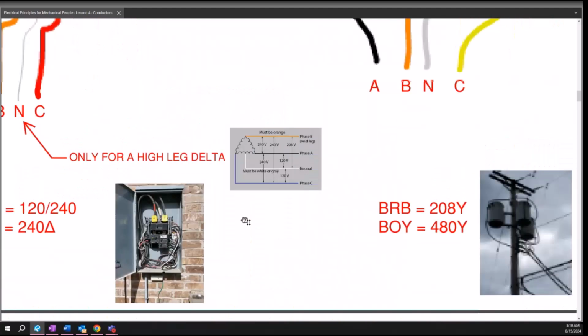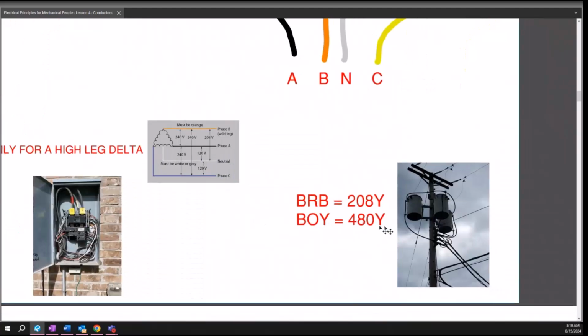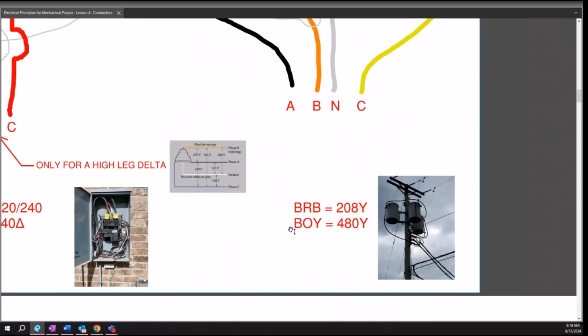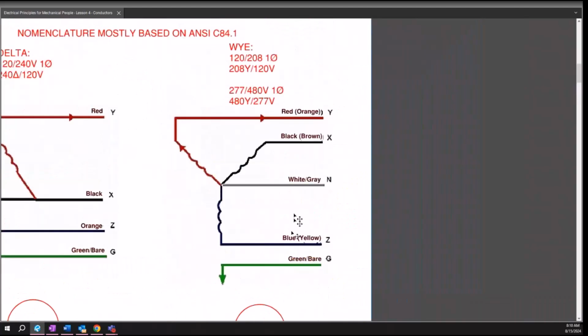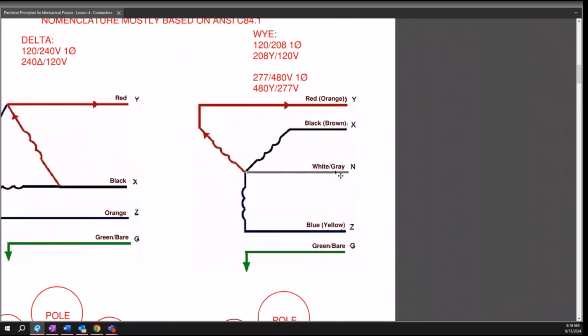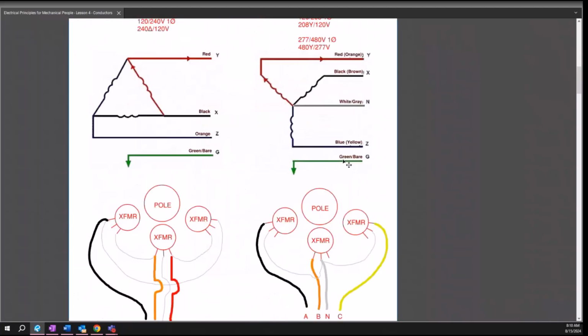But the color coding for the 208 or the 480, I always remember it: black, red, blue for 208, or brown, orange, yellow for 480. I don't know where that came from. I picked that up one day, probably from somebody else. But that's how I always remember it, and you can see that reflected here. You got black, red, and blue. And then you've got brown, orange, and yellow. And obviously, white, gray, always going to be neutral, period, across the board. That's a given. Same thing with the ground, green or bare copper. That's always going to be a given across the board.